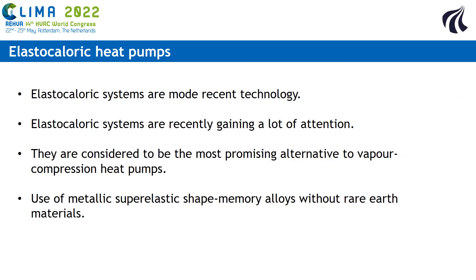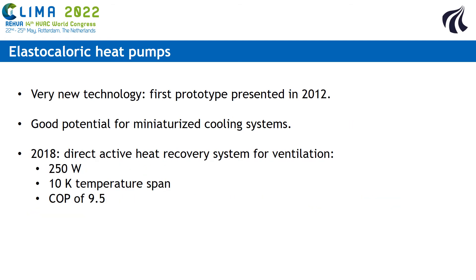The elastocaloric systems are a much more recent technology, but they have been gaining a lot of attention recently, and they are considered by some as the most promising alternative to vapor compression heat pumps. Elastocaloric heat pumps use metallic super-elastic shape memory alloys that do not contain any rare earth materials. The elastocaloric technology is quite new, and the first prototype was presented in 2012, but it has good potential for the miniaturization of cooling systems. In 2018, a direct-active heat recovery system for ventilation was tested with a power of 250 watts, a temperature span of 10 kelvin, and a COP of 9.5.